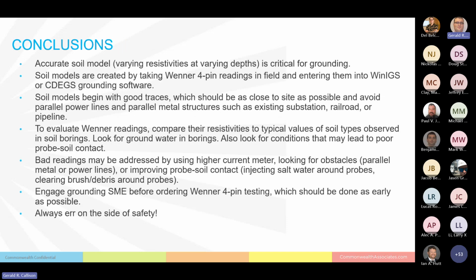So with that, let's go into conclusions. An accurate soil model with varying resistivities at varying depths is critical for grounding. Soil models are created by taking Wenner 4-pin readings in the field and entering them into WinIGS or CDEGS grounding software. Soil models begin with good traces—those lines on which the Wenner 4-pin measurements are taken at increasing horizontal spacing—and they should be as close to the site as possible, but avoid things like power lines or parallel metal structures that might throw them off.